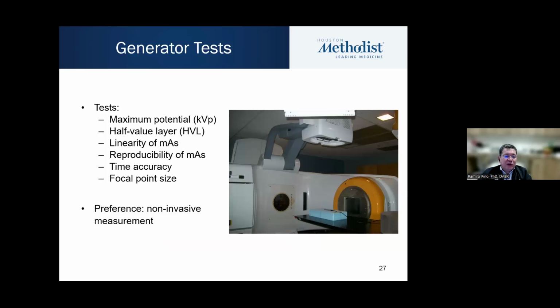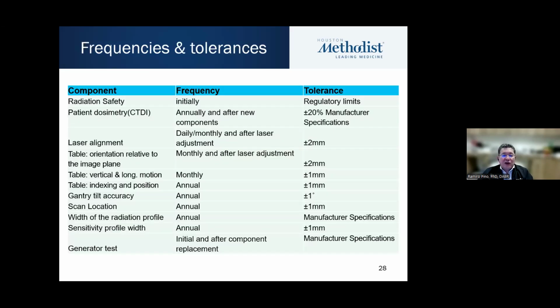The generator test will test the performance of the X-ray tube itself: the peak kilovoltage, the half value layer, which is related to the beam quality, the linearity of the milliamp-seconds, its reproducibility, the timer accuracy, and the focal spot size. Typically, we would like to use a non-invasive way, and there are several products out in the market that could be used for that purpose. The frequencies and tolerances are important.